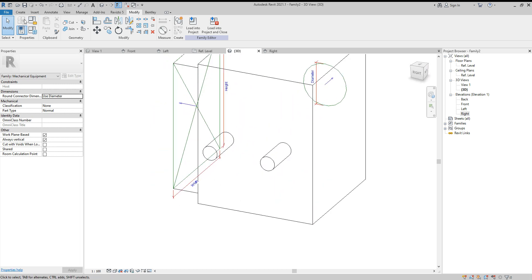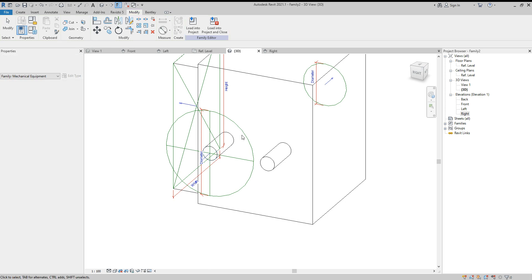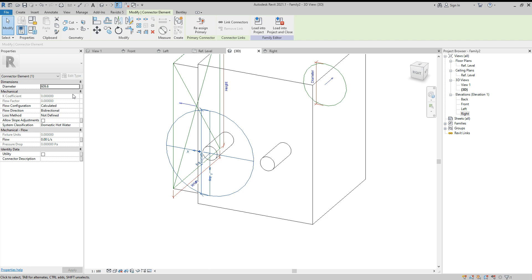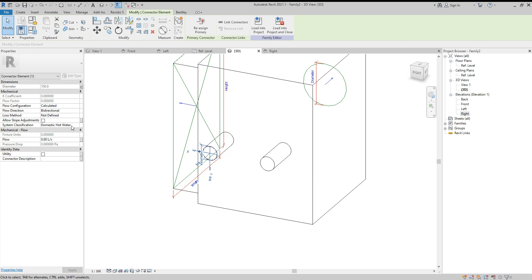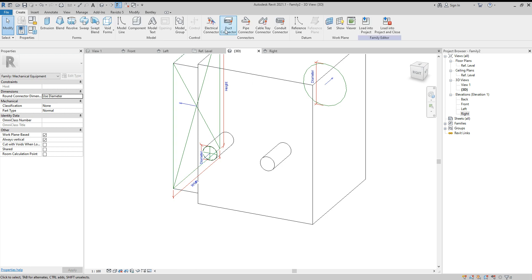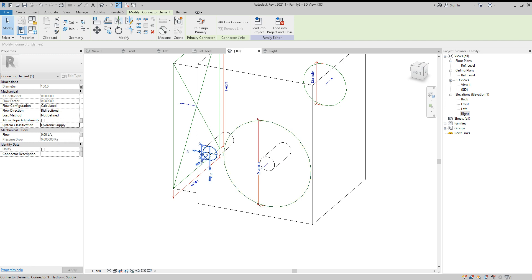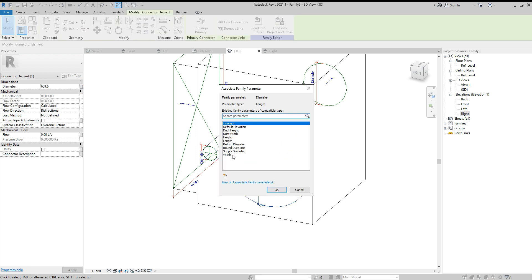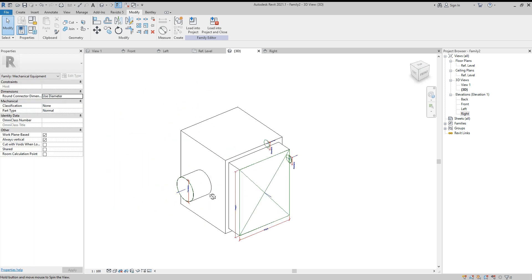For the pipes, go to Create, Pipe Connector, select the first pipe face. Set the diameter to 'Supply Diameter' and the system type to Hydronic Supply. Then add another Pipe Connector on the second pipe face and set it as Hydronic Return with 'Return Diameter'.